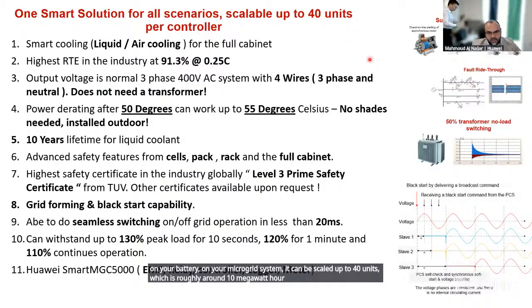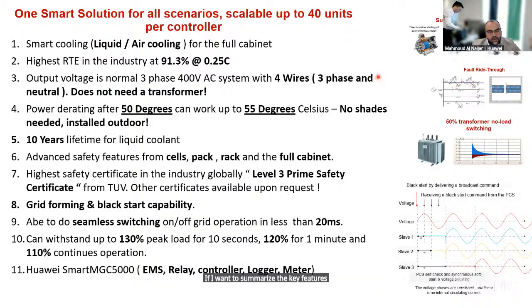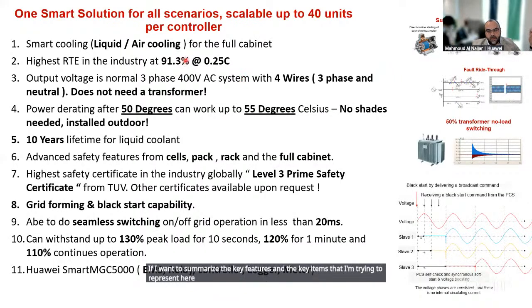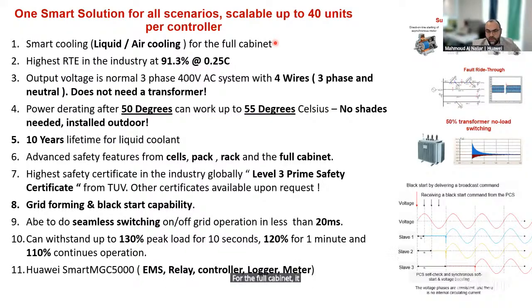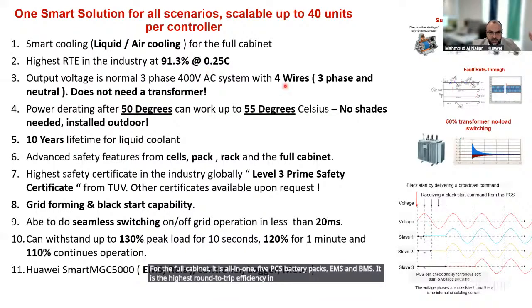If I want to summarize the key features and the key items that I'm trying to represent here, it has a built-in cooling system for both liquid cooled and air cooled for the full cabinet. It is all-in-one: 5 PCS, battery packs, EMS and BMS. It has the highest round-trip efficiency in the industry, reaching 91.3%. So that makes sure you have more usable capacity in your batteries.